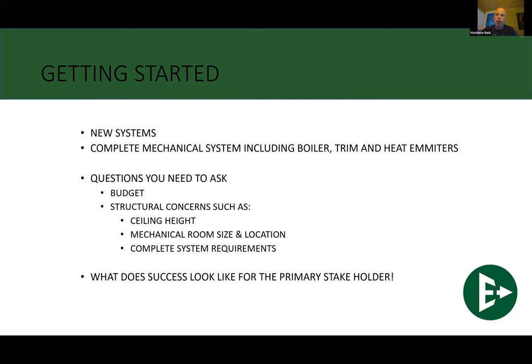So these are things you want to run past your customer beforehand, let them know what they're going to be up against, or the mechanical room size. Lots of times nowadays, I've seen mechanical rooms going under the stairways, usually in the basement, maybe in a small little closet. Is it going to be even big enough to put anything in that they want to do? Maybe they need a 100-gallon indirect, but they only have room for a small combi boiler. These are things that we can work with and work around, but we need to explain to our homeowner that we need more room to put the equipment in than what they're looking for.